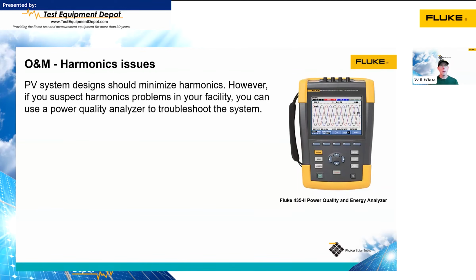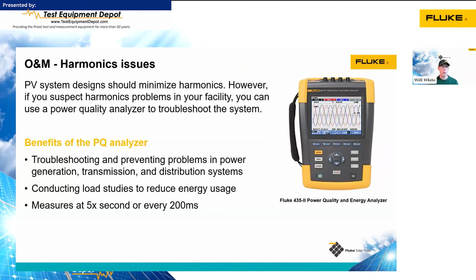Now, harmonic issues can be a problem. Usually it's coming from the utility or from a load in, say, a manufacturing facility. Very, very rarely do we have problems with the inverters creating power quality issues. Some of these power quality meters can also be used to conduct load studies. And those are really good if we're including behind the meter energy storage to offset loads. We can identify how much energy those loads are consuming and then size our energy storage system appropriately. As I mentioned, some of these power quality meters can also measure transient voltage spikes, so they can see those very fast increases in voltage.